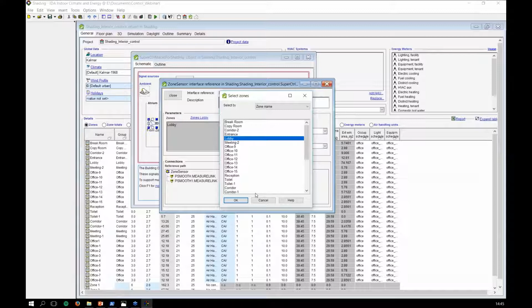If I have a list of zones here, I also have the option to apply a function on those, either to take the minimum or the maximum of these signals, or an average, some variation of average. So in this case, from the lobby, I'm taking daylight, and it doesn't matter what I put in apply function because it's only one zone.